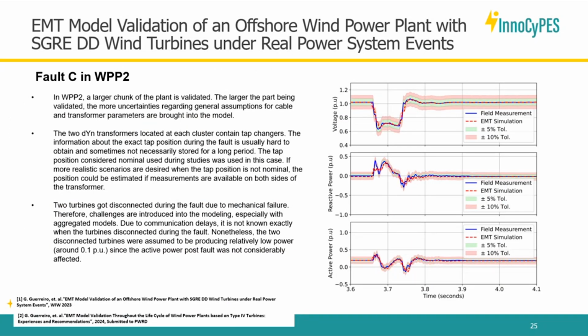And finally, what we have here is a two-phase fault on the other wind power plant. Here you have to remember that we validated a large chunk of the plant. There are two DY transformers that also have tap changers, and we don't really know the value of the tap changer. This isn't something that gets included in all the measurements and recordings, so it's a bit tricky.